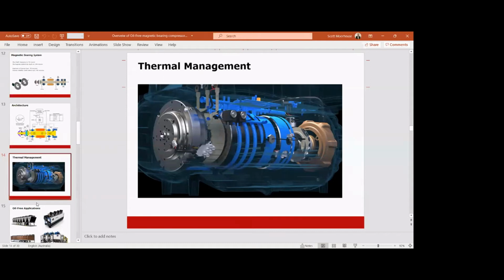So we have solenoid valves that will pulse liquid refrigerant into these cavities. So we have an electronics cavity, which will do the inverter, and then we have a motor cavity. Each one of these valves will control that. One will do the motor and one will do the electronics. And we have a number of sensors over the motor and electronics to determine how much liquid refrigerant we need to put on to cool the electronics. Once it has gone in as liquid into two phases and superheated the gas, the electronics path will go back into the second stage, and the motor cooling will go back into the first stage, because it's a two-stage compressor.